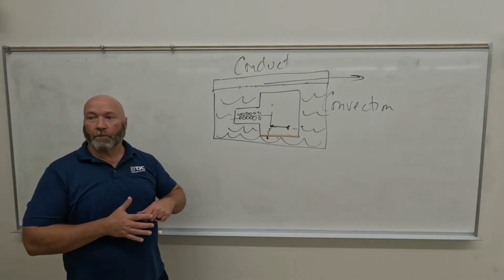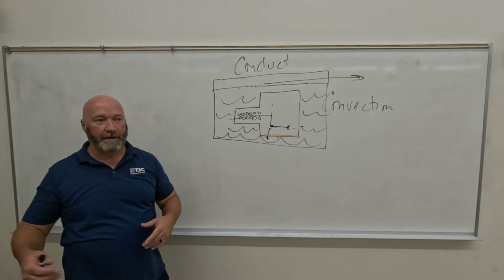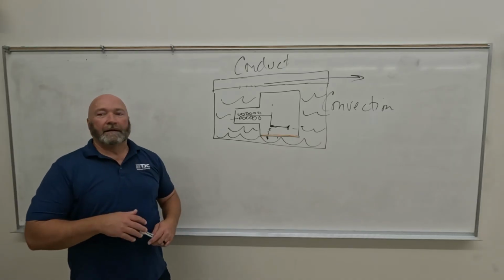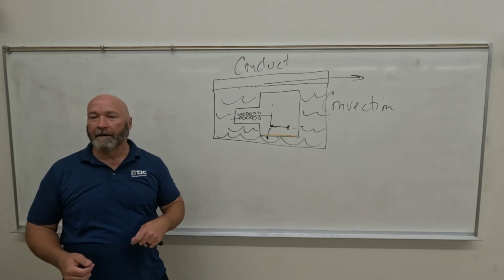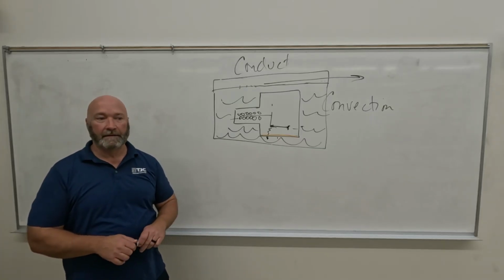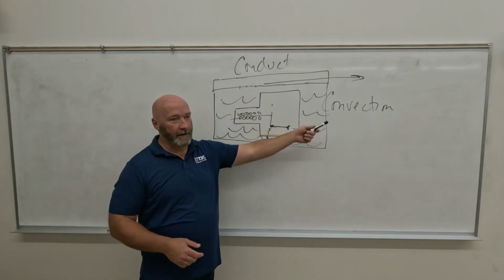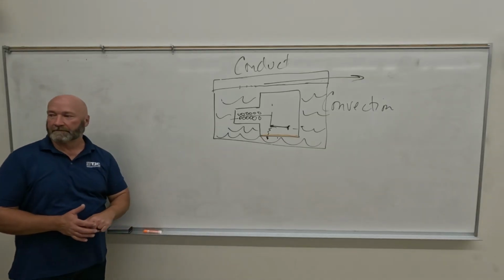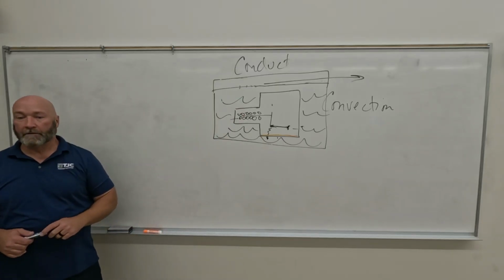Okay? So what do you need to know about all that stuff? The arcing is later in the semester. I was just trying to explain how the tube is going to get destroyed. With the exception of possibly rough handling, you banging a tube around, it's going to be from one thing primarily, and it's going to be heat. That's the main thing that kills the tube. Ways that we get rid of the heat will be on the test, but the specifics of the tanning and failure of the bearings and all that, not. Any questions?